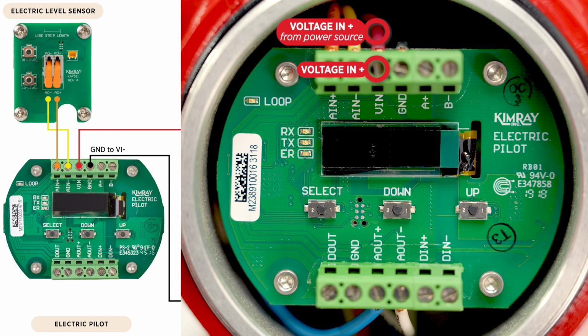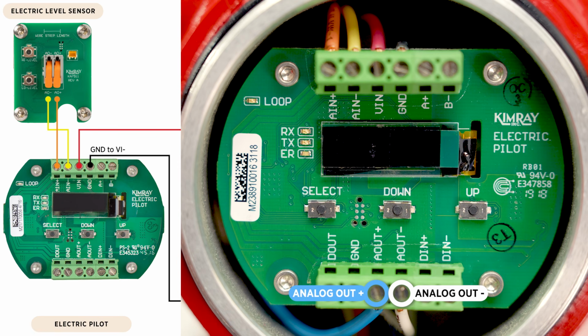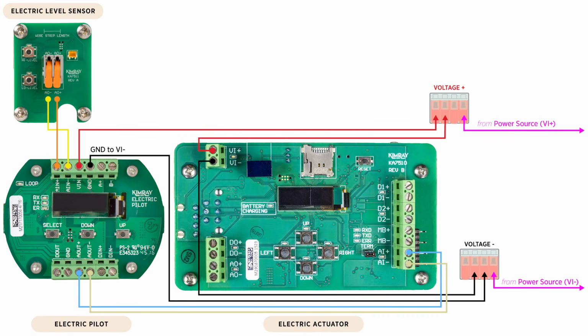Voltage positive will come into the voltage in positive on the pilot. Voltage negative will go into the ground terminal. The analog pilot output positive and negative will run to the analog input positive and negative on the actuator.